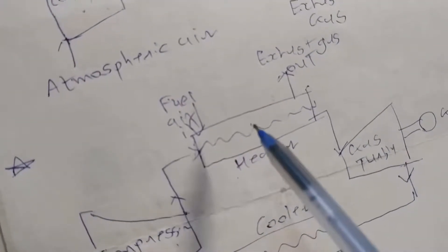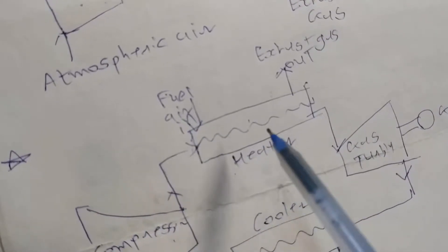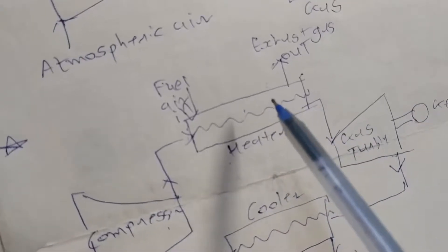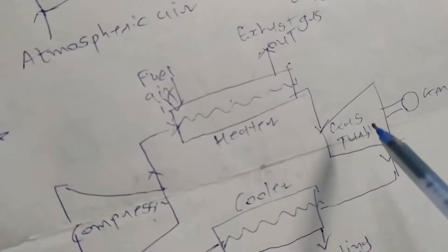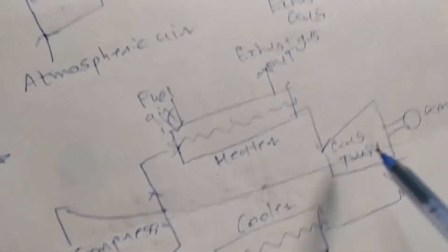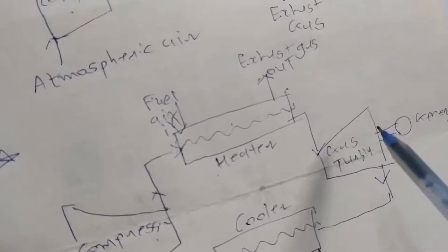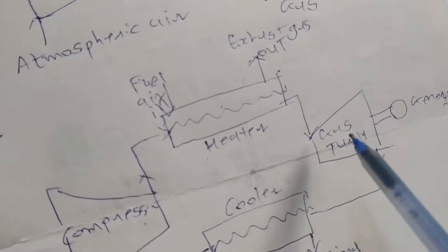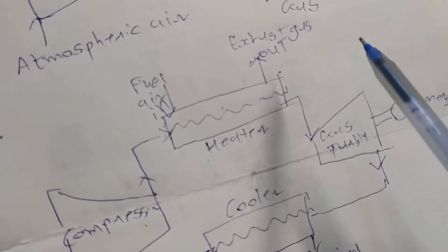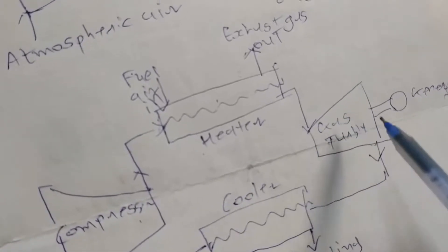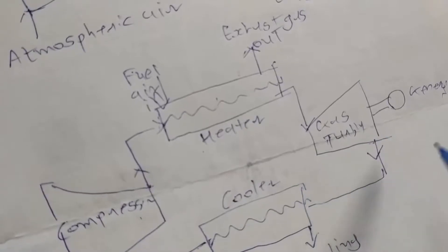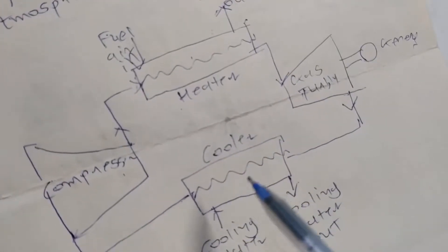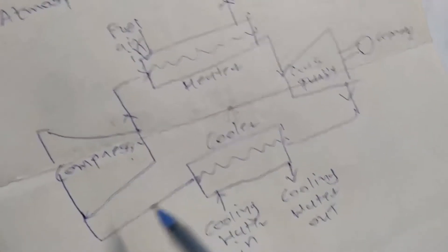While in the tube, heat is exchanged between the fuel fluid and the air coming from the compressor. This high temperature and high pressure air then goes to our gas turbine. Because we don't mix fuel directly with air here, erosion and corrosion will not occur in the closed cycle gas turbine — this is the main benefit. After the air is used, we don't let it go out; we cool it back to its normal temperature so we can use it again.